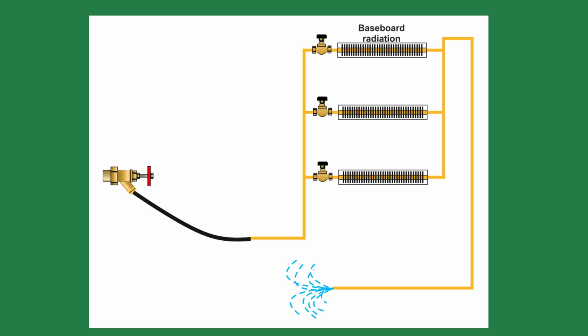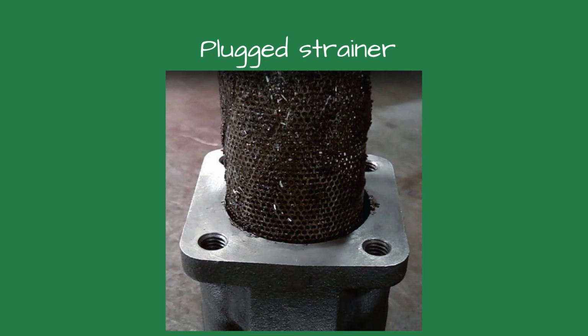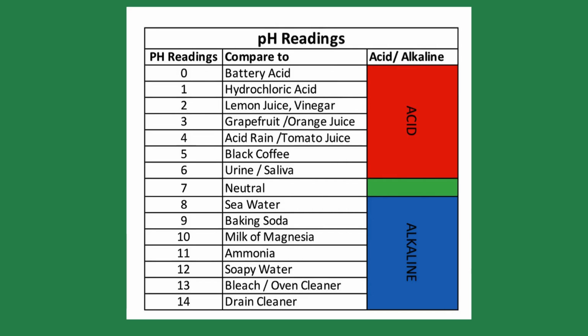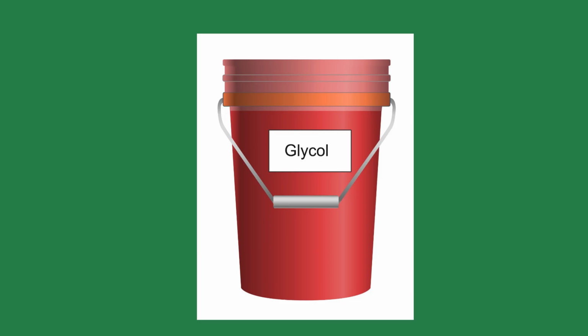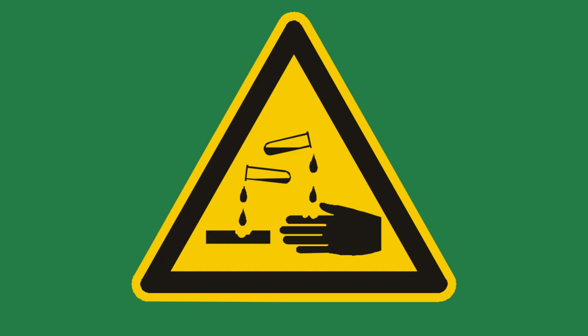Flushing means running clean water through the existing system piping to remove contaminants: dirt, sludge, rust, scale, oils, flux, and chemical residues. Think of it like rinsing a dirty glass before pouring in fresh water. Without this step, whatever was in the system ends up circulating through your new boiler and circulator from day one. Flushing does more than remove debris. It also restores a neutral baseline for water chemistry. This is crucial if the system previously used glycol. Over time, glycol breaks down and becomes acidic, which accelerates corrosion and damages components. Flushing ensures that the new boiler is not immediately exposed to these harmful byproducts.